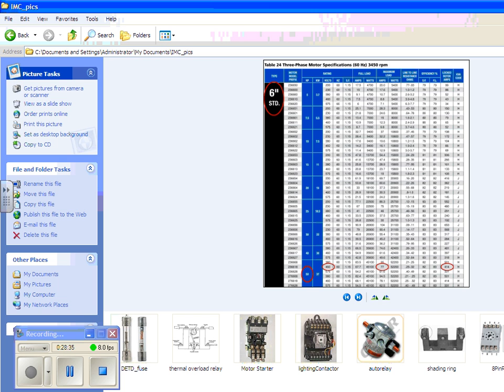Now there's some things in here you need to learn just by looking at this chart, and some of that you can't do by just looking at the chart. We're going to do a couple of selections. If we were going to have a 40 horsepower motor, and we're going to operate it on 480 volts or 460 volts, what size starter would we need? We could probably, at 480 volts, use a size 3, because look at polyphase. We're assuming it's polyphase. And in 480, 3 goes all the way up to 50 horsepower.